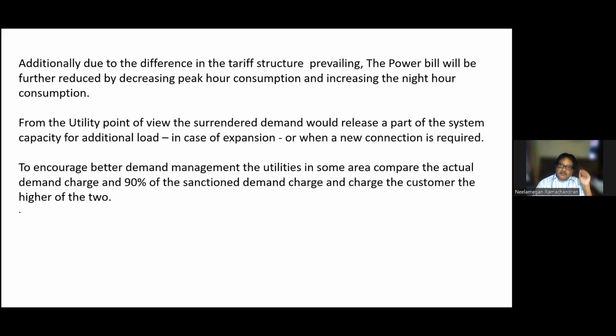Additionally, because of the tariff structure, we also got a 5% rebate by running at night. By surrendering the MD, the power station can use the released MD for further expansion or for any other new connection. That's why they encourage us to use less maximum demand, because they charge 90% of the sanctioned demand charges. Whether you are using the fully sanctioned demand or using less, you have to pay a minimum of 90% of the sanctioned demand. So we have to be careful to use 90 to 100%. Otherwise, we will be using 70% of the sanctioned demand and paying for 90%.